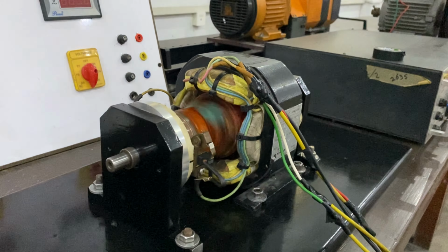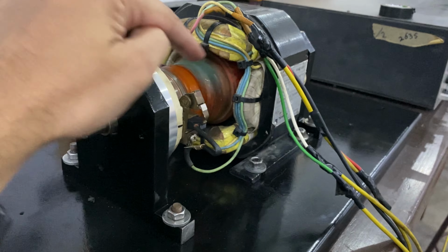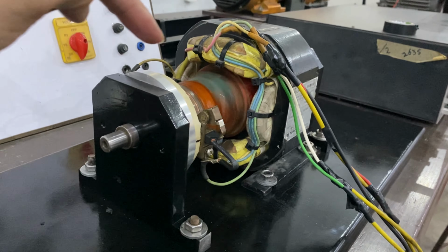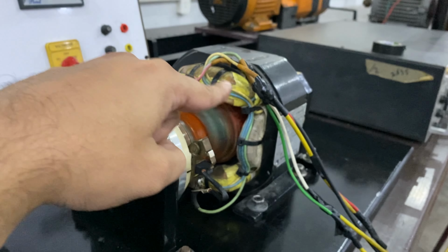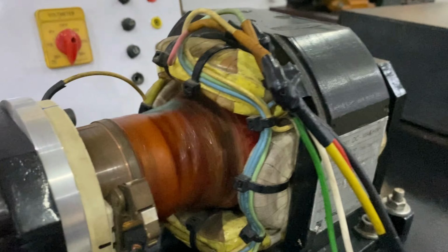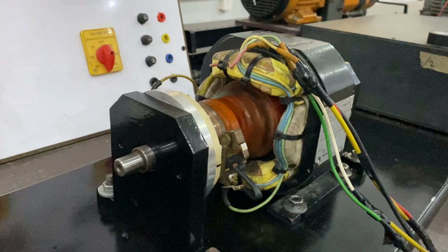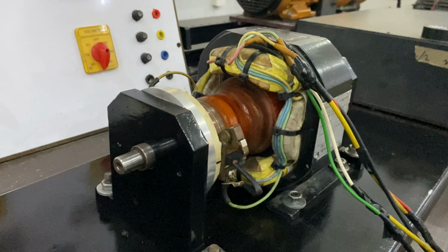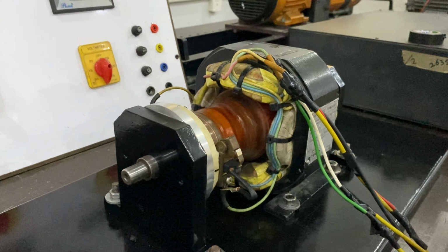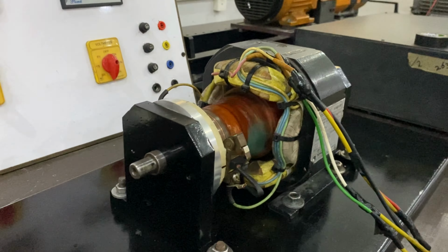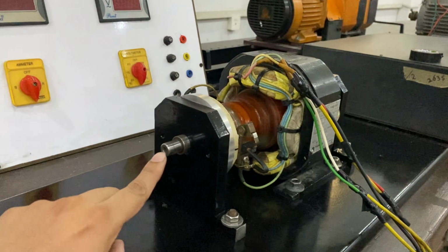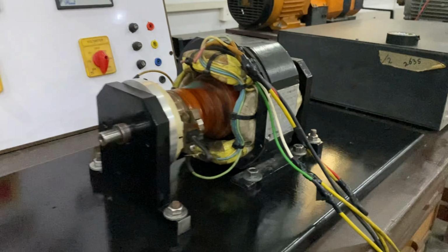So if I summarize the list of the parts, you have the armature, the rotating part, commutator segments, armature core, and the shaft. These are the rotating parts, and in the static part you have the field winding, pole shoes which are there inside, and the field winding core. The field core and the armature core are made up of thin laminated sheets to reduce the eddy currents, and the material of these cores is selected to minimize the hysteresis losses, as we have discussed in the theory class. So these are the parts of your DC machine. Mechanical parts are these ones. Shaft is also a rotating part, and there are the ball bearings inside that you can observe from here.